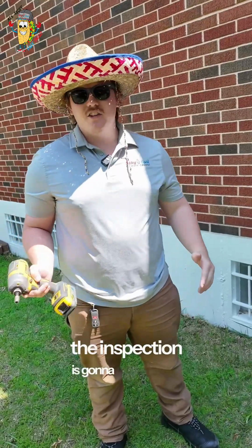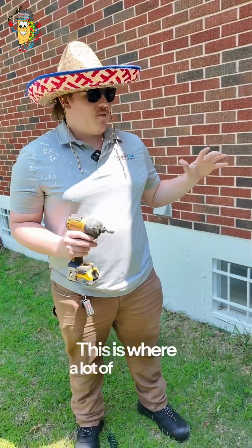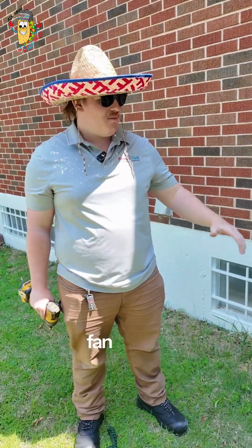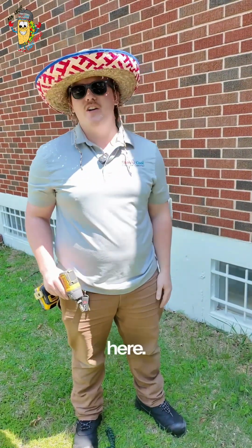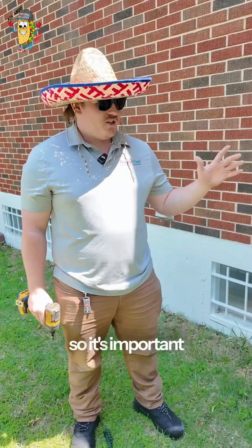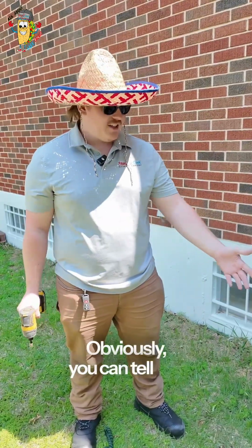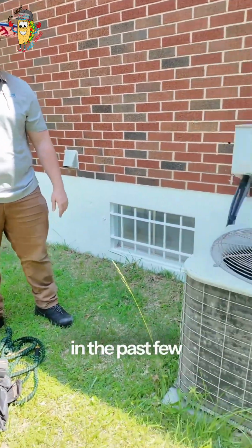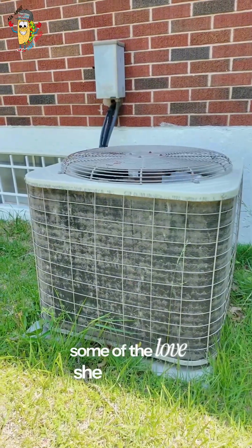So next part of the inspection is gonna be checking out the outside unit. This is where a lot of important components are, your compressor, fan motor. All your refrigerant gets pumped through here. It's basically the heart of the system, so it's important to get it checked out and get it cleaned. Obviously you can tell this unit's not been very well loved in the past few years, so we're finally gonna give her some of the love she deserves.